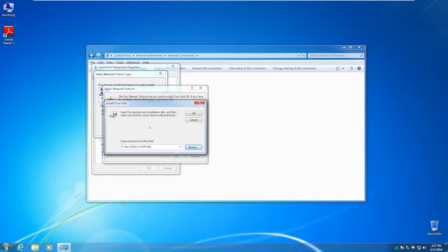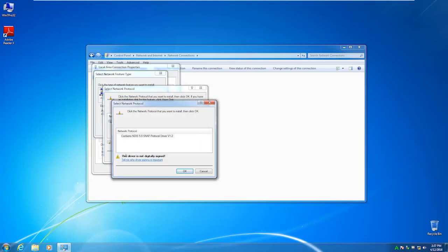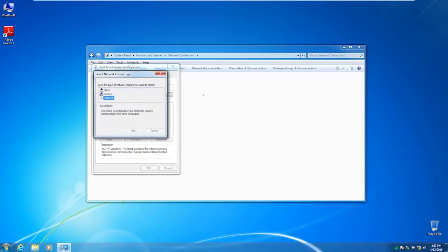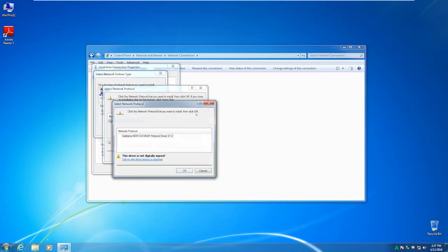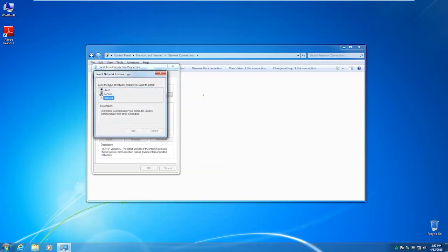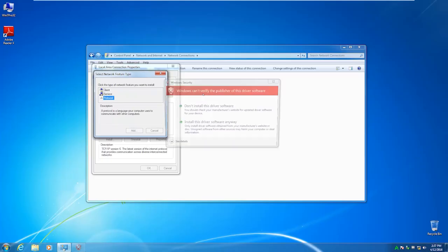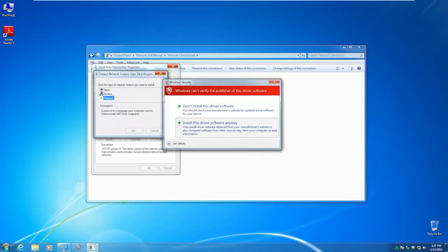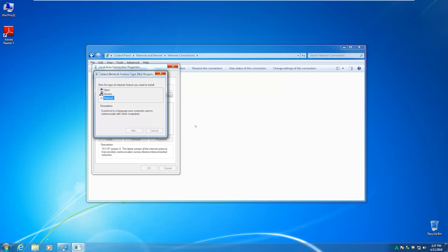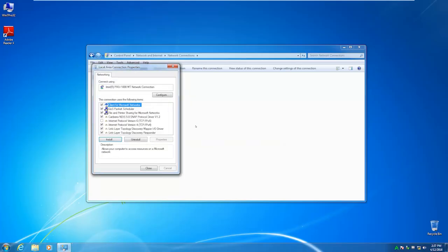After you select the AIM SNAP5.INF file, you will see this window. Click OK. You will get a warning. Press OK. You should see Canberra NDIS 5.0 Snap Protocol listed. This will bind to every network device it finds. You only want it connected to whatever you are using to communicate with the desired MCA. If you have more than one network connection, you have to check the Snap Protocol off for the others.